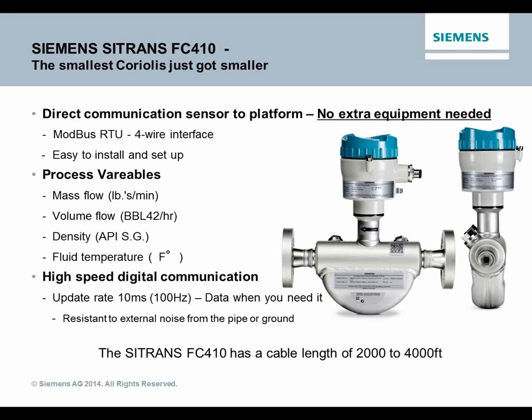So what happens is that as the tube is filled with ever-increasing densities of fluid, the resonant frequency of that particular tube goes down. The tube is more comfortable vibrating at a lower frequency. So the density of the fluid affects the resonant frequency of the tube that it's in, and the resonant frequency is achieved by that frequency with which the tube naturally wants to be at, actually where the power to drive the tube is least for maintaining a stable frequency.